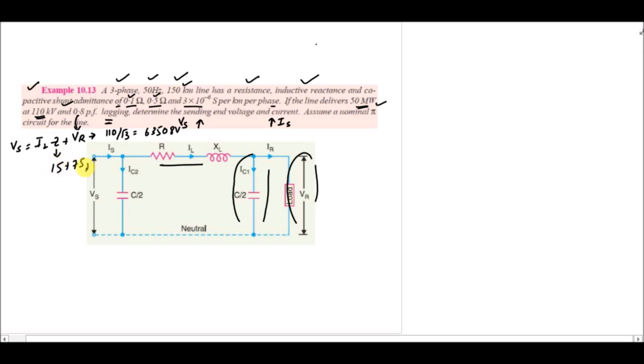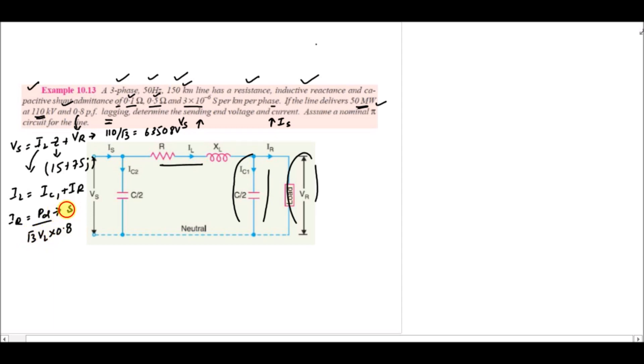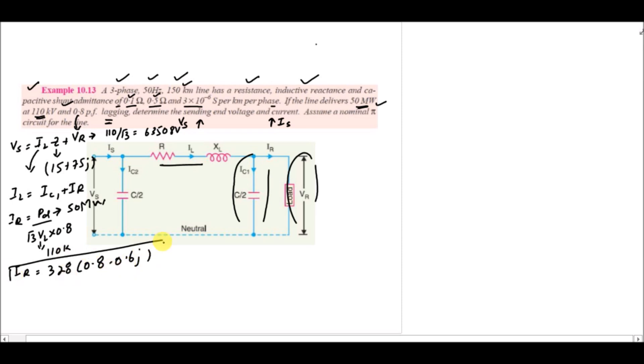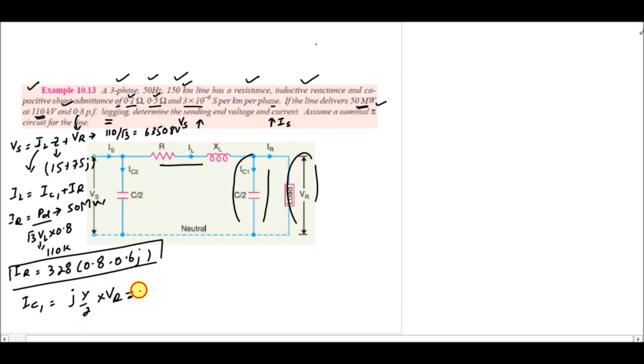We do not know IL directly, but from the circuit IL = IC1 + IR. The receiving end current IR = P_delivered / (√3 × V_line) = 50 MW / (√3 × 110 kV), giving IR = 328∠(0.8 − j0.6), i.e., IR = 262.4 − j196.8 A. For IC1 = j(Y/2) × VR = j(45×10⁻⁵ / 2) × 63,508, giving IC1 = j14.3 A.